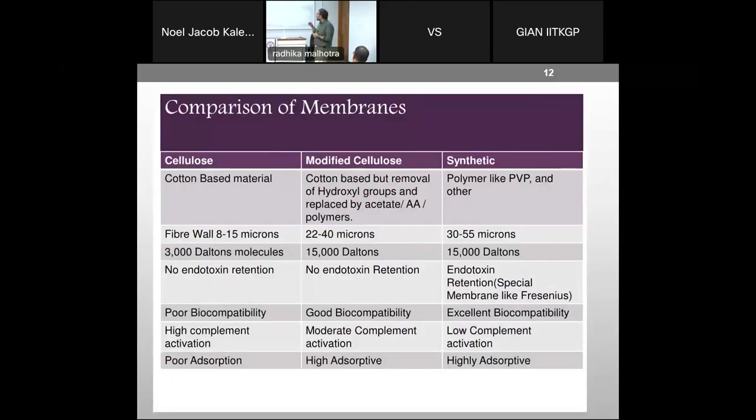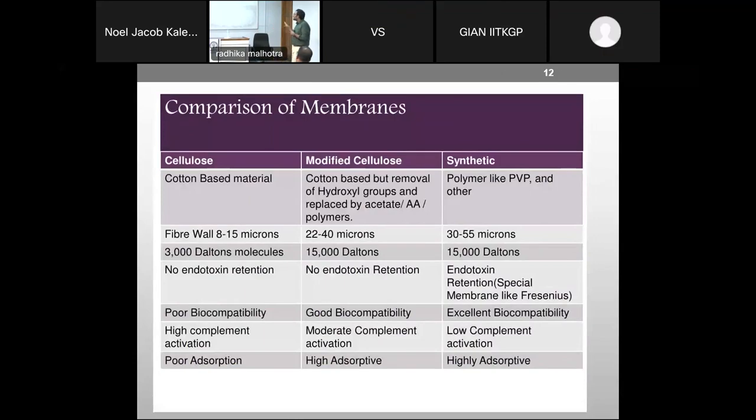Okay, comparing the membranes, you can have cellulose, modified cellulose or synthetic membranes. You can see these relations for what it is made of and what the fiber wall is. But the third row talks about what kind of molecular weight solutes it can remove. The cellulose could remove only 3000 Daltons, but the modified and the synthetic ones can remove up to 15,000 Daltons. Endotoxin.